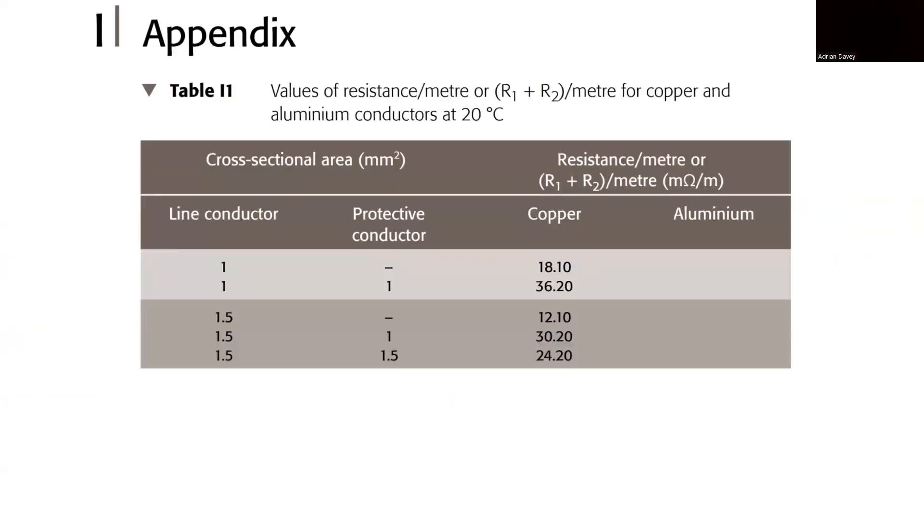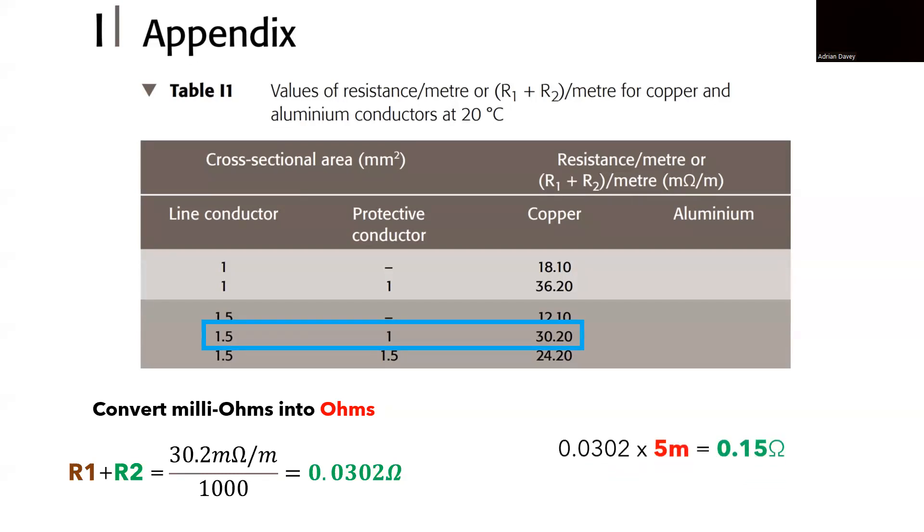To confirm the readings displayed by the meter and ensure their consistency with the expected values, we can refer to appendix I of the on-site guide. This section provides resistance values for R1 plus R2 milliohms per meter. If you are working with twin and earth cables featuring a 1.5 mm squared line conductor and a 1 mm squared CPC, our combined R1 plus R2 resistance amounts to 30.2 milliohms per meter. Converting from milliohms to ohms is a simple matter of dividing by a thousand, making 30.2 milliohms equal to 0.03 ohms. If we consider the 5 meter distance mentioned in the previous slide, our calculated reading rounds down to approximately 0.15 ohms.